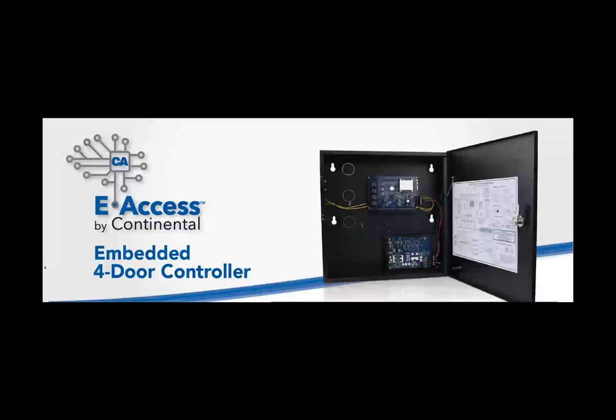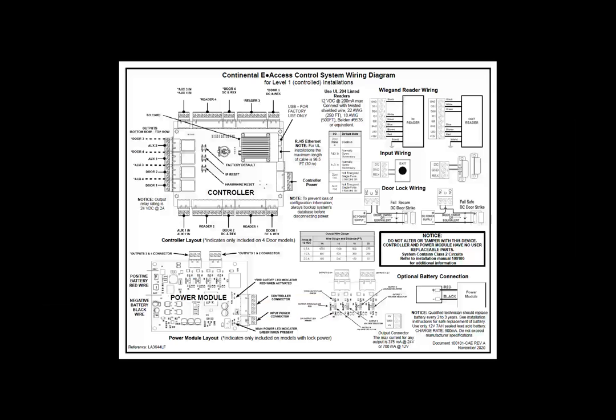The eAccess embedded 4-door controller supports 4 doors with 2 readers on each door. In addition, it contains 8 relays, 4 for door locks and 4 for auxiliary relays. It also contains 3 inputs for each door. One for rex, one for door position switch and one auxiliary input. The 4-door controller is also available with a power package that includes expanded power for door locks.